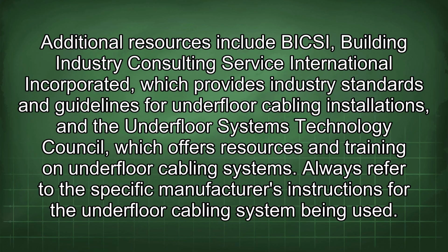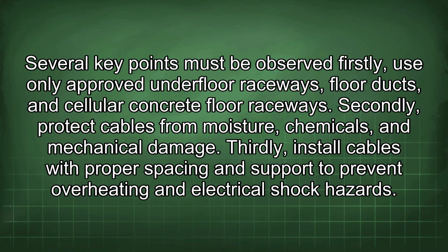Always refer to the specific manufacturer's instructions for the underfloor cabling system being used. Several key points must be observed. Firstly, use only approved underfloor raceways, floor ducts, and cellular concrete floor raceways. Secondly, protect cables from moisture, chemicals, and mechanical damage.